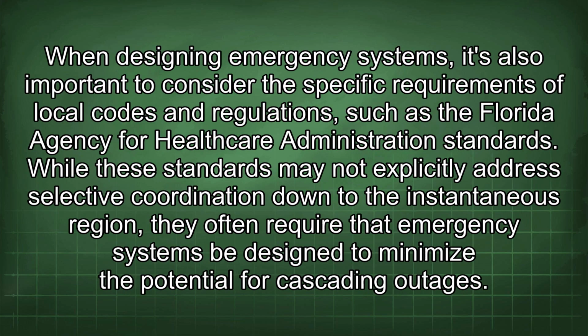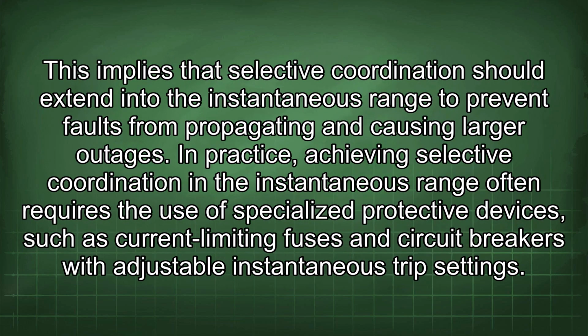When designing emergency systems, it's also important to consider the specific requirements of local codes and regulations, such as the Florida Agency for Healthcare Administration standards. While these standards may not explicitly address selective coordination down to the instantaneous region, they often require that emergency systems be designed to minimize the potential for cascading outages. This implies that selective coordination should extend into the instantaneous range to prevent faults from propagating and causing larger outages.